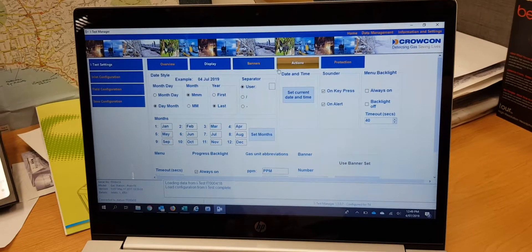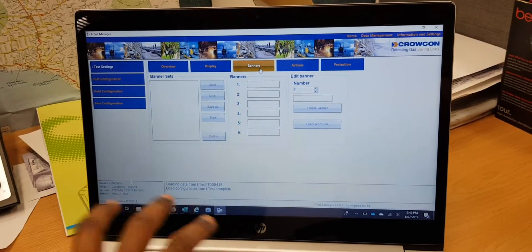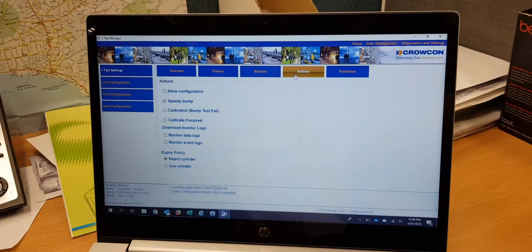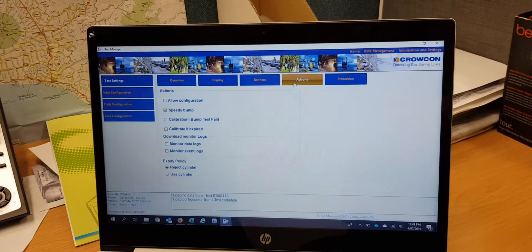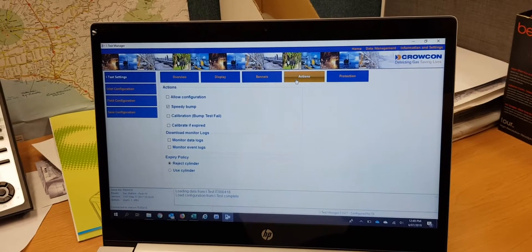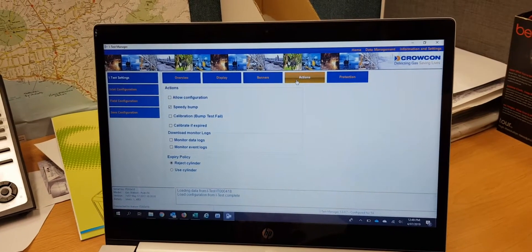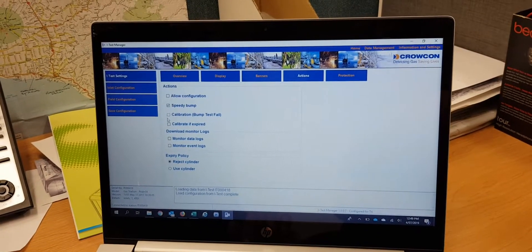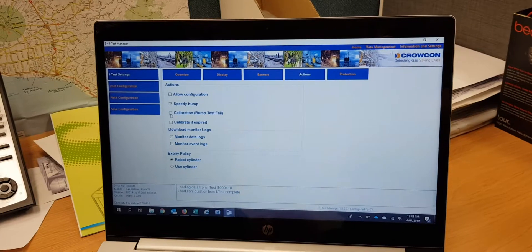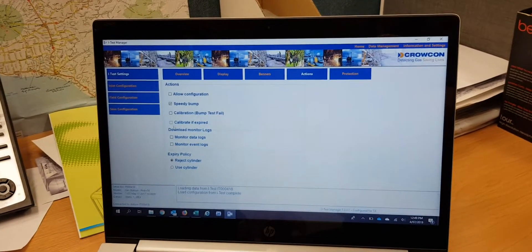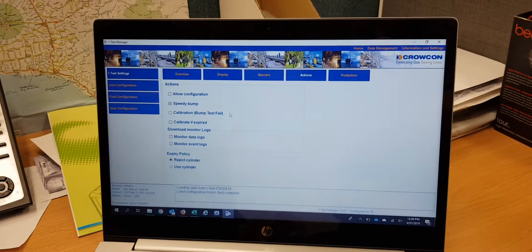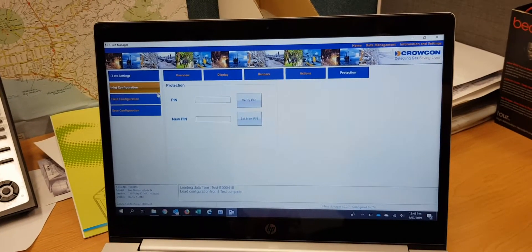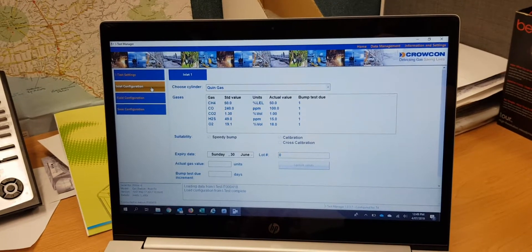These are the basic configuration settings — dates, setups, and how the banners appear. Companies can put their logo here. Here you activate what kind of bump test you want: 'Speedy' bump test allows calibration only when the bump test fails or when the calibration due date has expired. We'll leave it to speedy action. You can also configure a PIN number, and then there's inlet configuration.